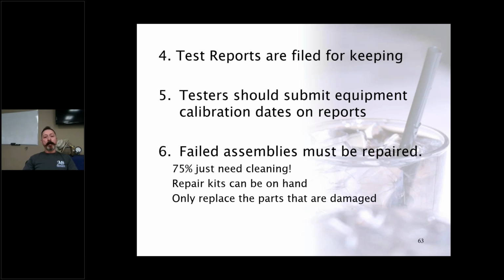Testers should submit equipment calibration dates. Some of these gauges are pretty sensitive instruments, and they sometimes get banged around and lose their sensitivity. So these things have to be calibrated on an annual basis as well. That's often recorded on these test reports and is a requirement of a tester as well. They have to keep all this equipment in good shape, as their own equipment. And if you have a test report that you're getting filled out, that information should be on the forms.